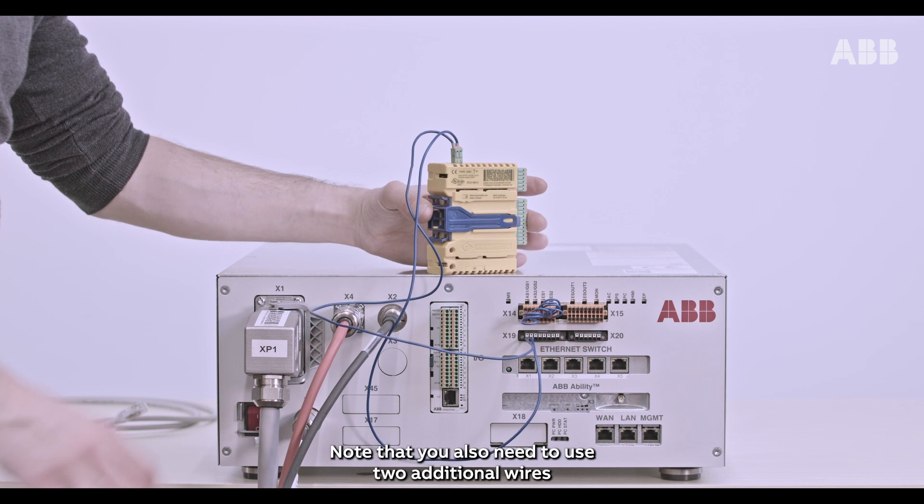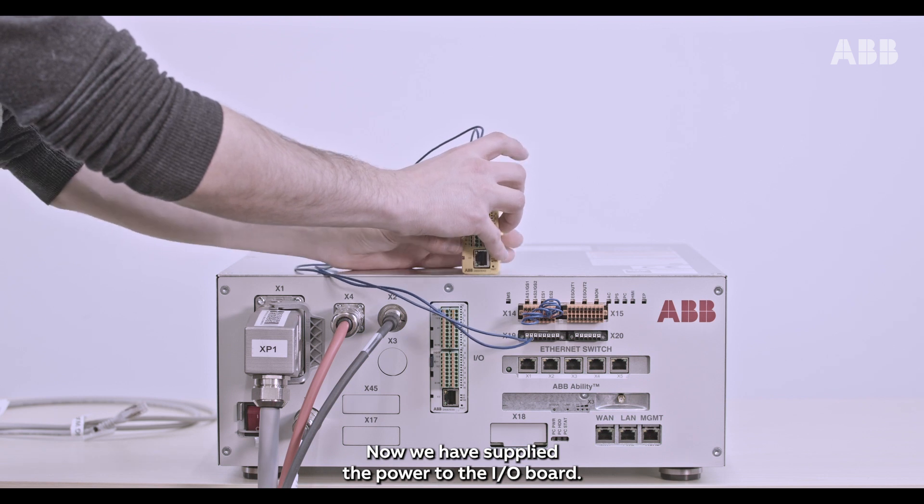Note that you also need to use two additional wires to provide 24V power to the output socket of the I.O. board. Connect the opposing ends to the X19 connector of the controller. Now, we have supplied the power to the I.O. board.